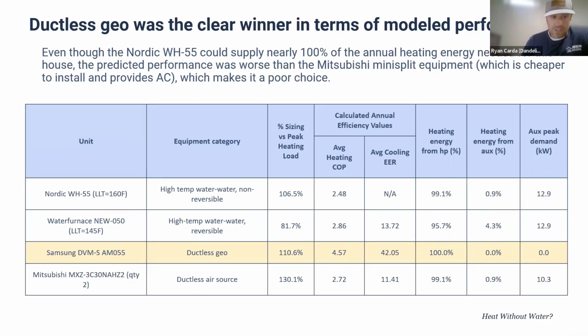Also interesting: that Nordic heat pump was able to make 160-degree water, meaning we could meet the peak load of the building. But the average COP value for that unit, because of the large thermal lift going from a 30-degree source to a 160-degree output temperature, was lower than the air source Mitsubishi unit for that home over the course of the year.